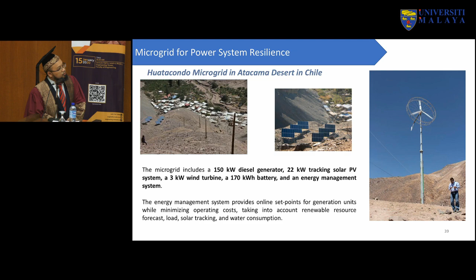But this work comes up with a new technique on a ramp rate control approach. We can see that if we use the normal technique, during photovoltaic operation the power being generated has a lot of ripple. So the system should be able to smooth it by injecting power from the battery. But the existing technique is not so effective because it causes the battery to work continuously. Whereas using the technique proposed in this work, the battery only works at certain times, so we can make sure the battery life lasts longer compared to if the battery switches on and off continuously.